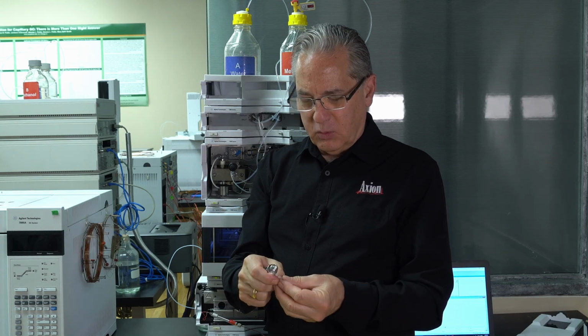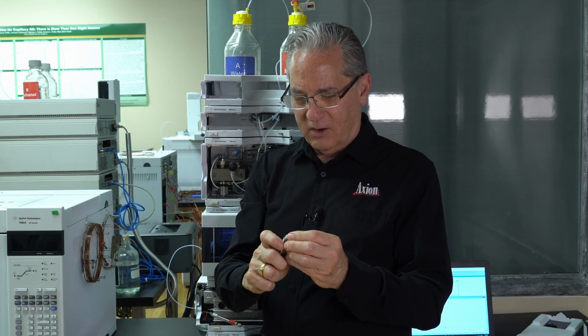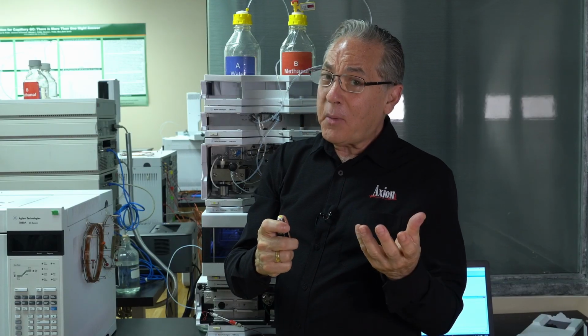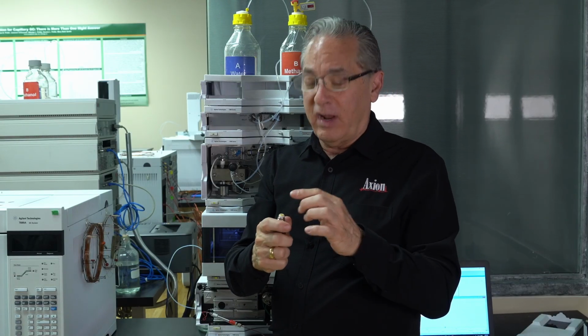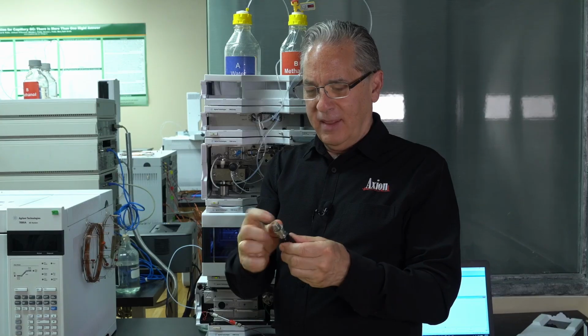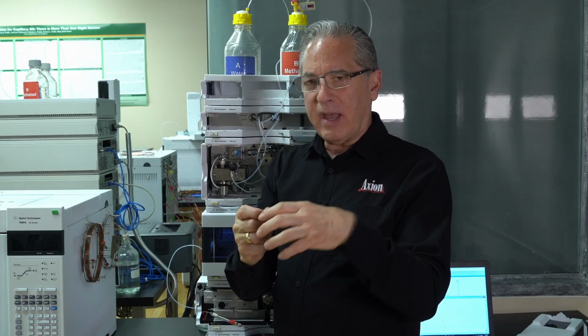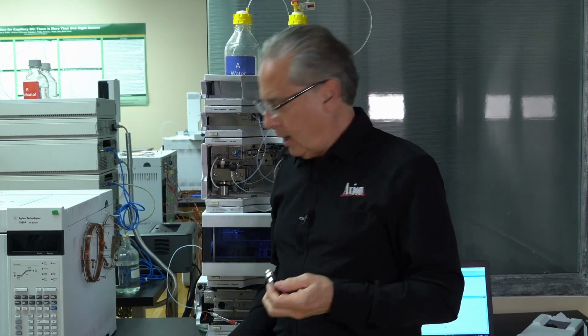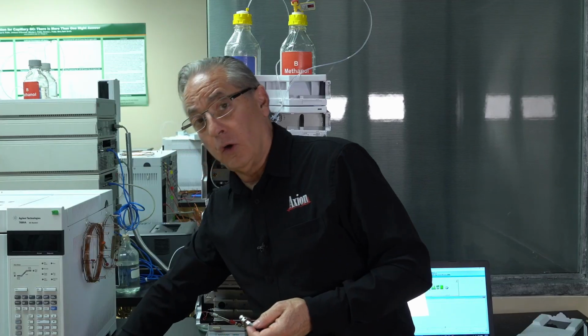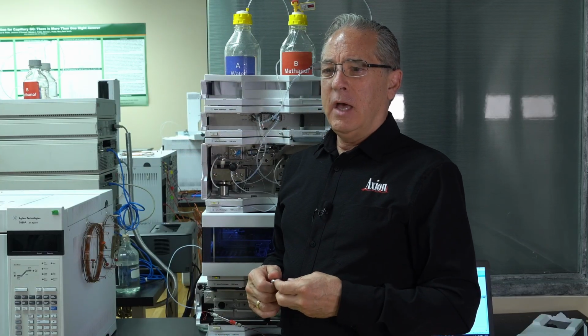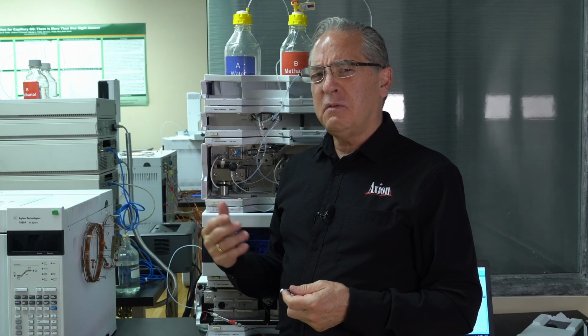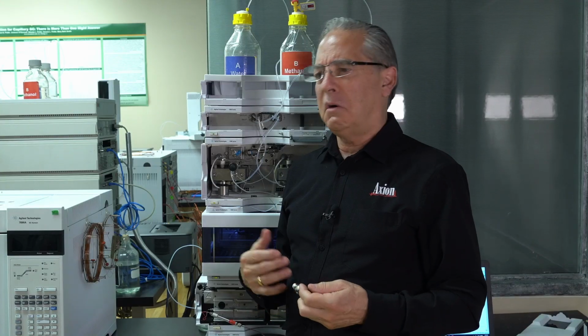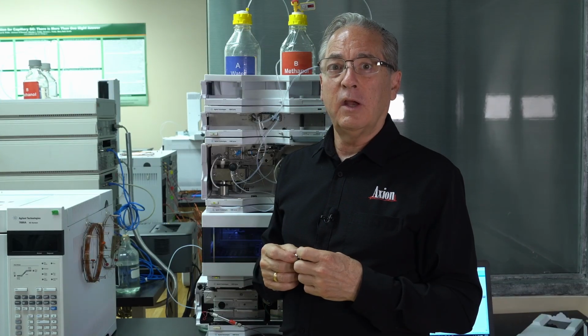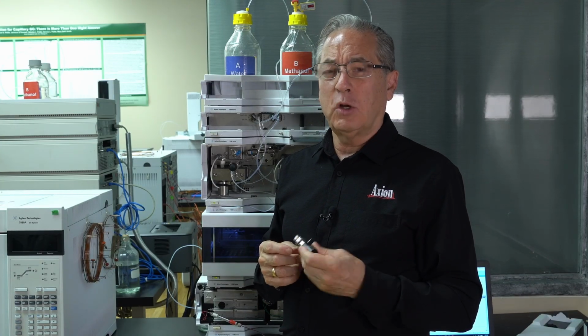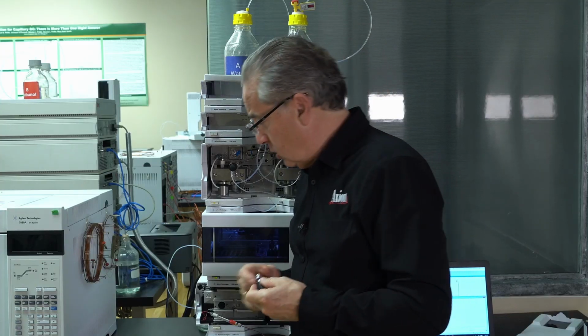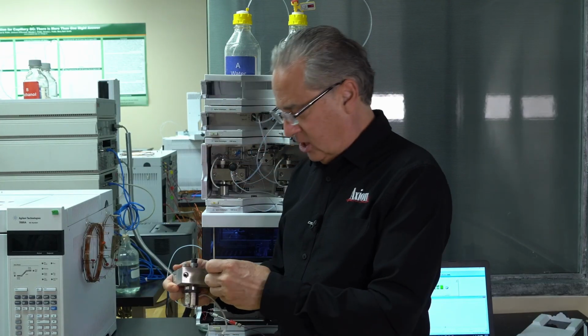I've never had to replace one of these. I mean, I've taken them out, put them back on 100 times. I don't know if eventually they wear out, but I have replacements, but I've never had to replace one. So you put this guy back on, that's the sealing surface, and when you screw it back on, you are good to go, and your filter is now clean. The filters will get dirty because of particulates in the mobile phase or just general growth here and there. So it is one of those preventive maintenance things that I do recommend you get on every once in a while and change them.